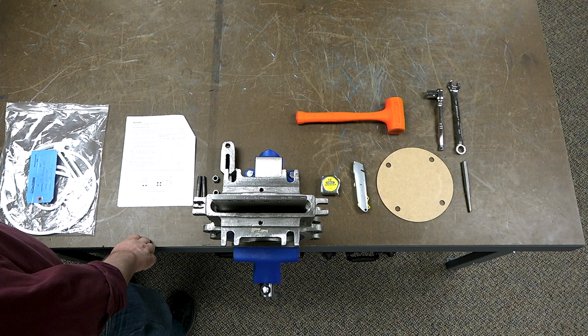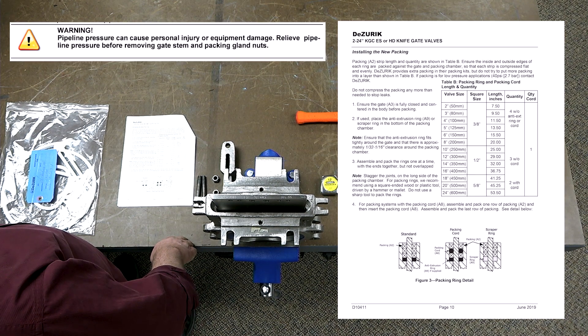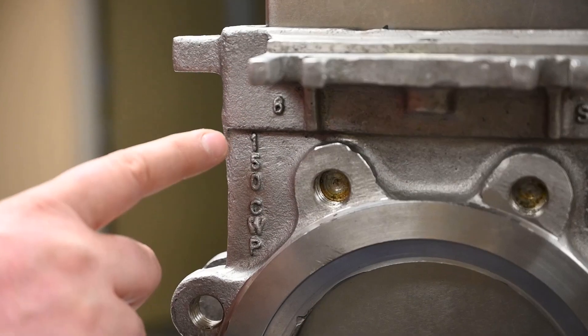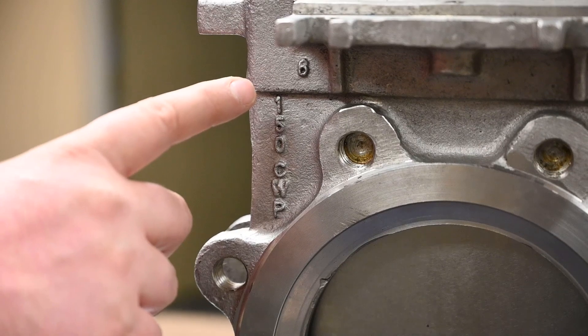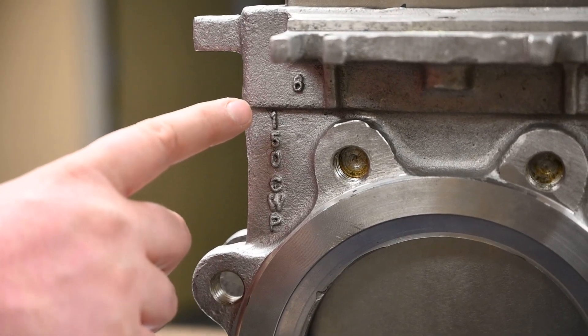The packing repair kit includes an instruction manual, otherwise known as the IOM. Be sure to follow all cautions and warnings in the IOM. In the IOM, you'll find a table giving the proper length for each row of packing and the number of packing rows for each valve size. Valve size can be verified on the body casting.